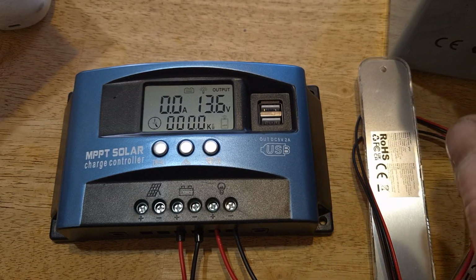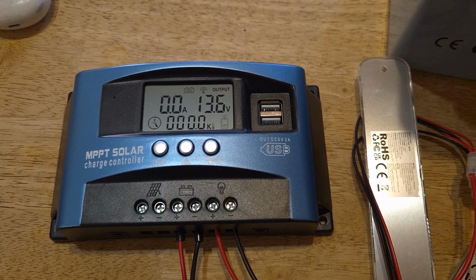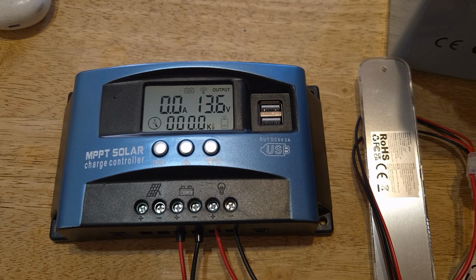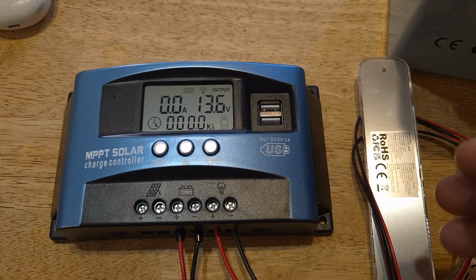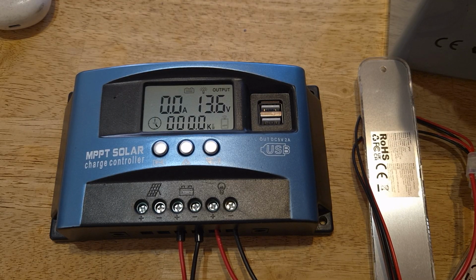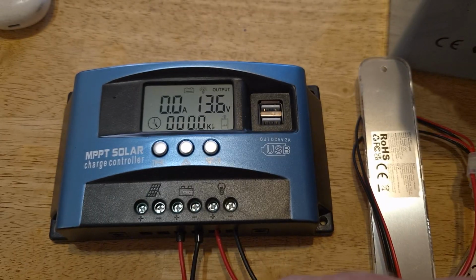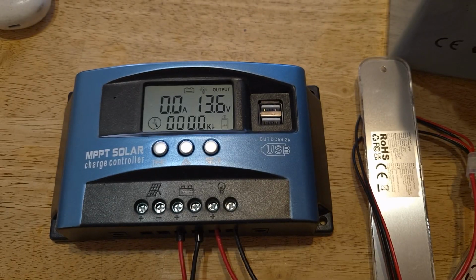This is where the magic happens, because your lithium batteries, like this one, advertise 5,000 cycles. Sometimes it'll last more, sometimes less. But they don't like to be fully discharged, they don't last as long. So if you want to double the amount of cycles, or get close to it, you want to set your low cutoff voltage to a minimum of 11 volts. Its default is 10.7, but I prefer it at 11, even 11.2. I'd rather have less of the cycle and have my battery last longer than use 100% of its capacity, which it doesn't like.